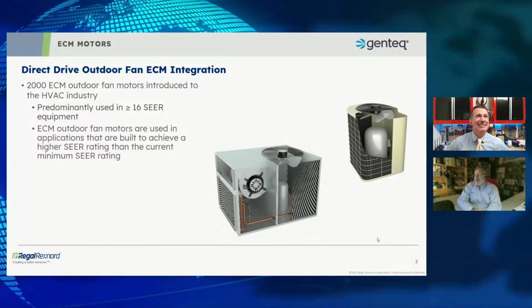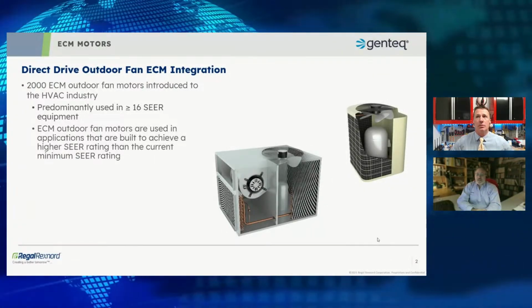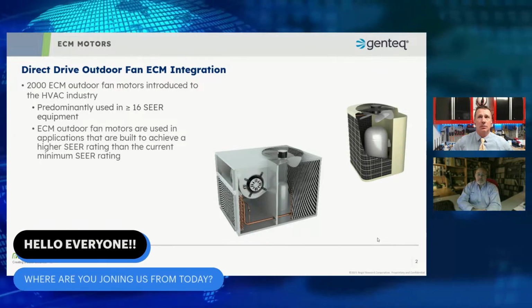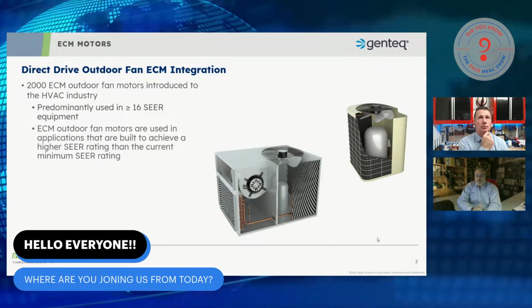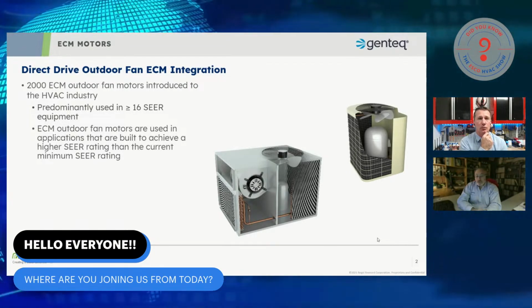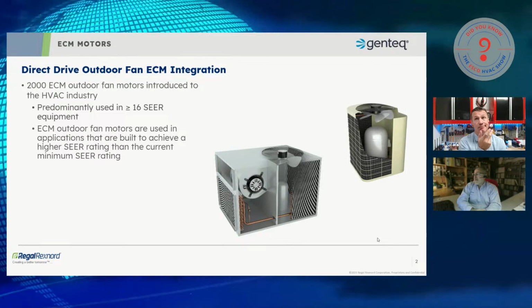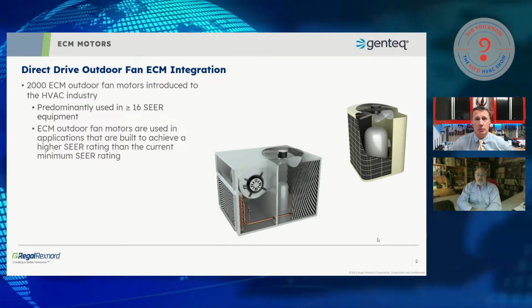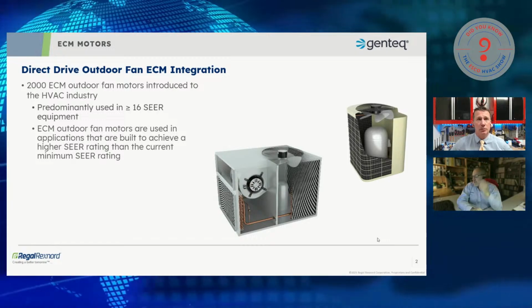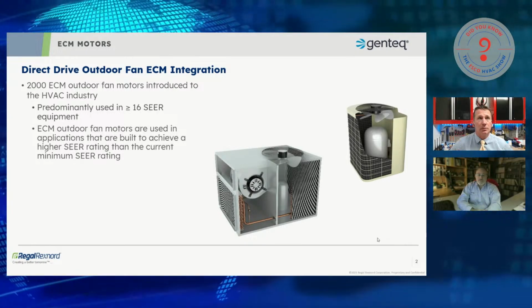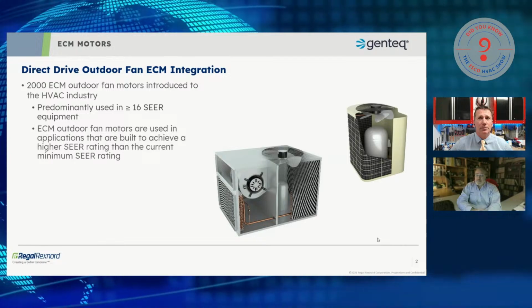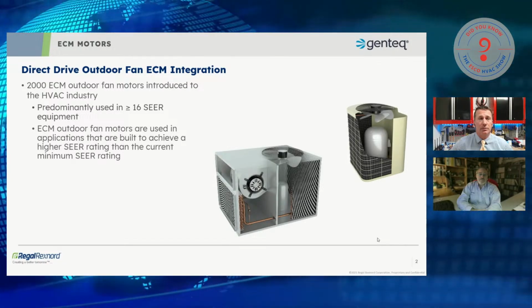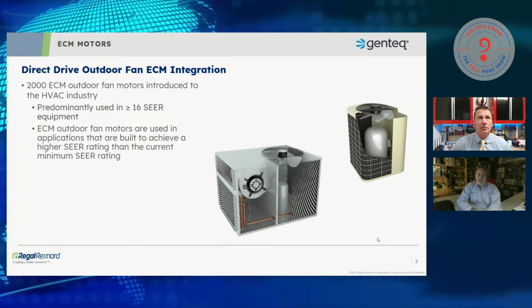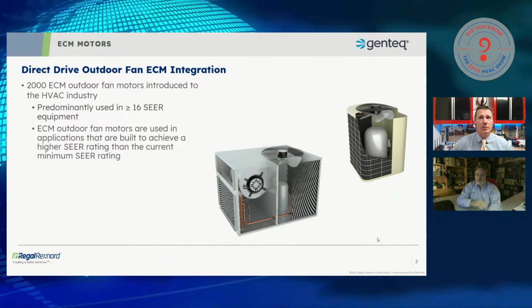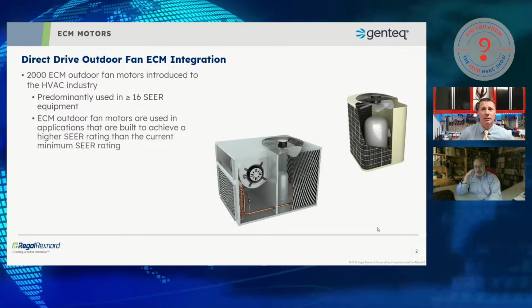So, direct drive outdoor fan ECM motors. We're going to talk briefly about when they began to become integrated into the industry, where you're likely to see them, why you may or may not be seeing them in your market, and why you may or may not start to see them in your market in the near future. We, Genteq, formerly branded GE Motors, introduced the ECM outdoor fan motor around the year 2000. They're predominantly used in 16 plus SEER systems. I do know some manufacturers use them in 15 SEER, but predominantly across the industry it starts at around the 16 SEER rating and up.